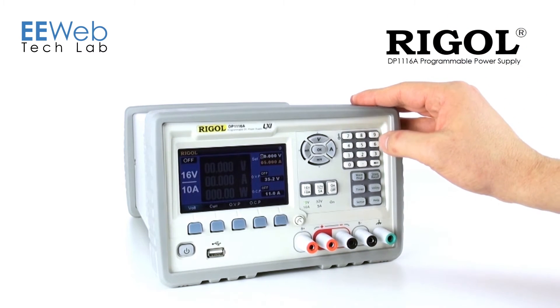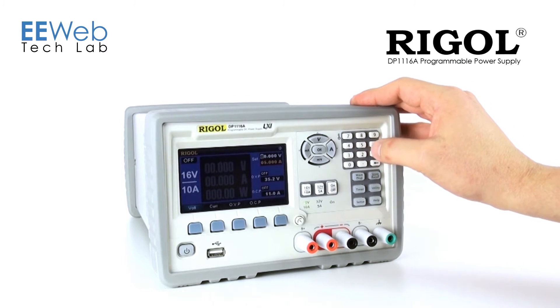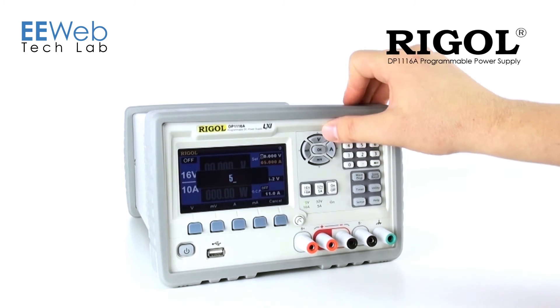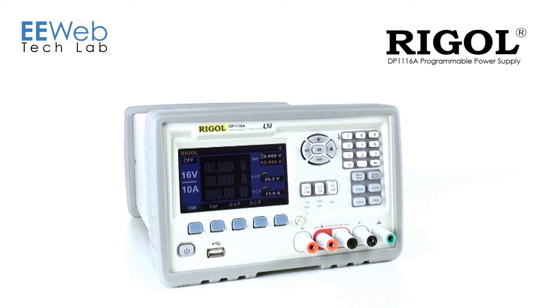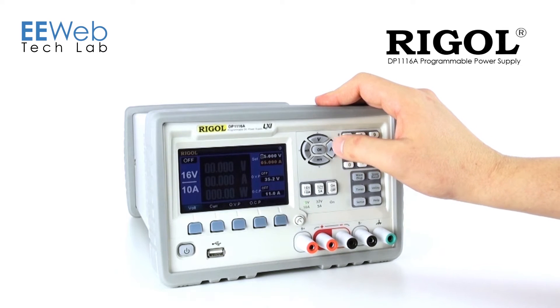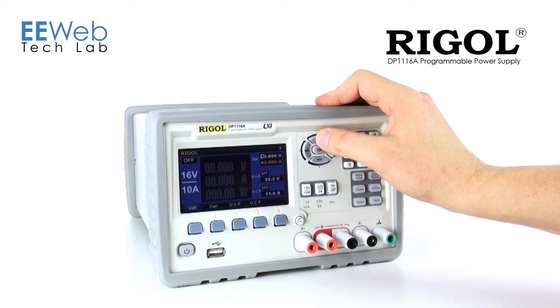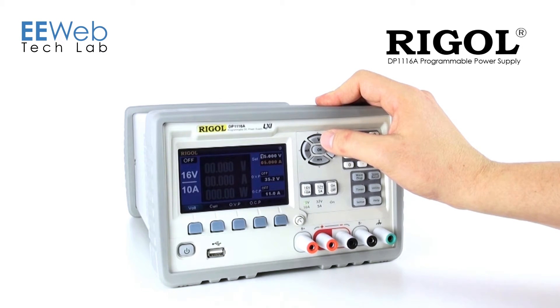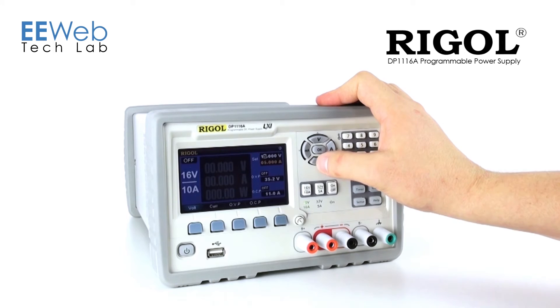Rather than using a knob to dial in your voltages, Rigol has included a keypad. So if I want to set the instrument to 5 volts, I simply press 5 and the volt key, and now I'm at 5 volts. You'll notice that this keypad serves multiple purposes. If I actually want to increase the voltage similar to a dial, I simply click the up button and you'll see it change from 5 volts to 15 volts. I can also dial this down as well.